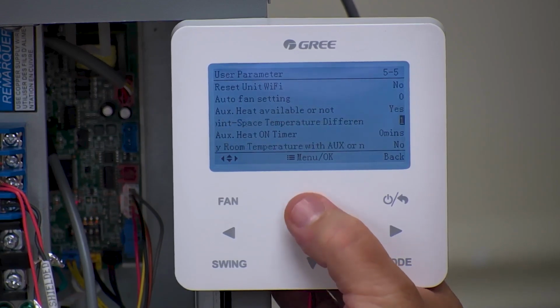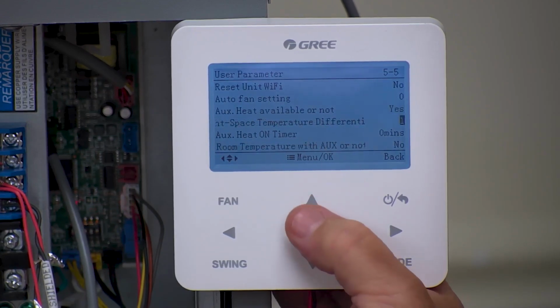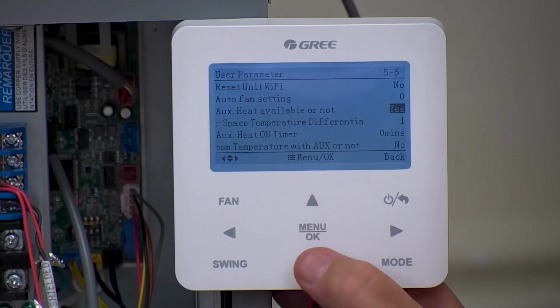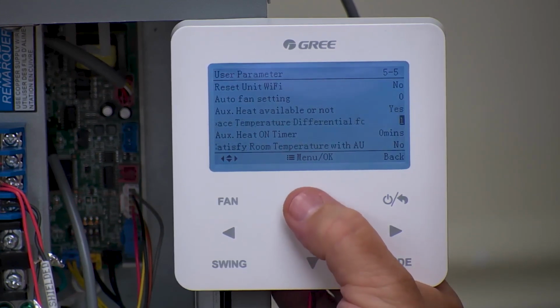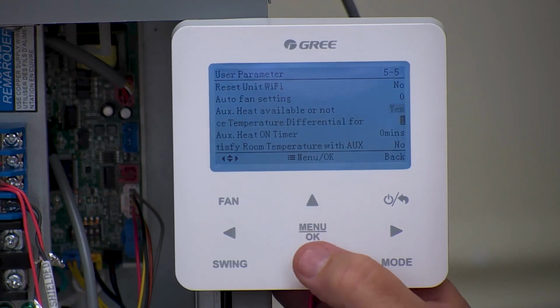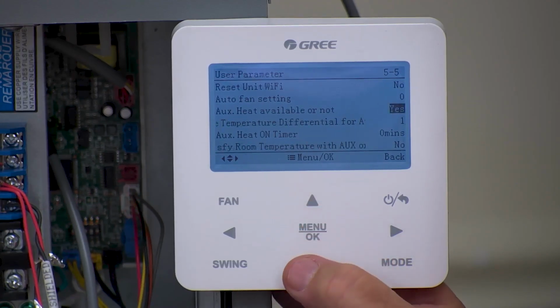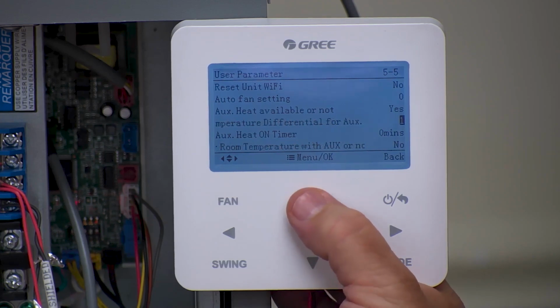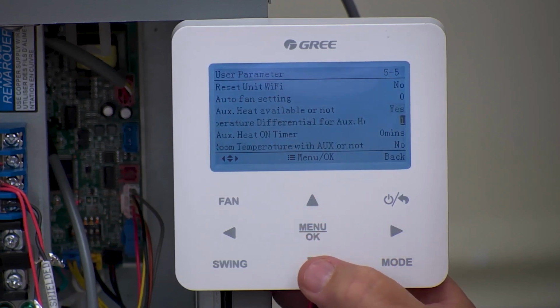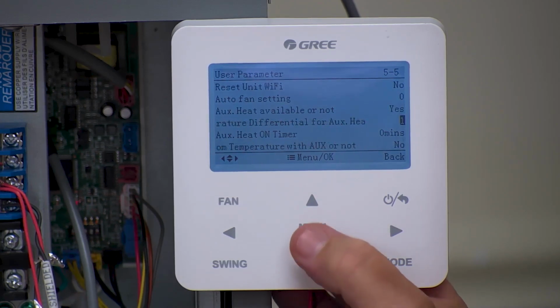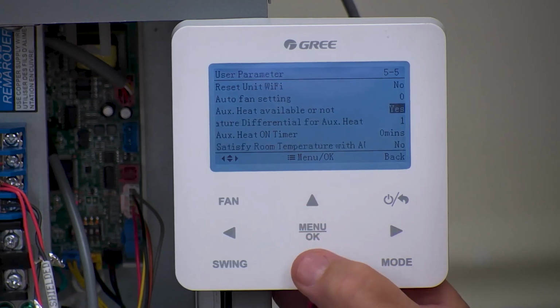So anyway, what that differential is, that's basically your differential between your first and second stage. So right now I've got it set to 1, and you can go between 1 and 10. So basically you can have this set up to where you've got a 1 degree differential between the heat pump running. If we slip another degree, then it's going to bring on the electric heat. If it doesn't slip that degree, it's not going to bring on the auxiliary heat.